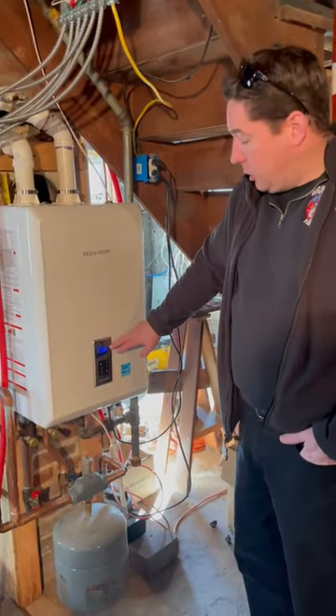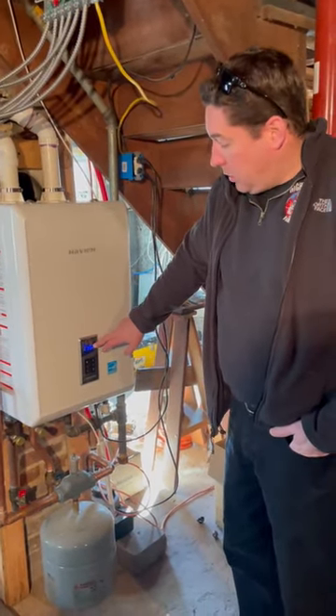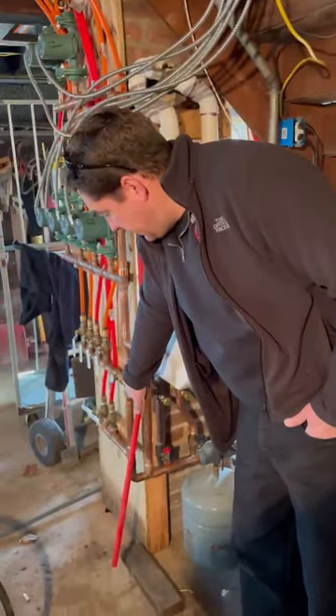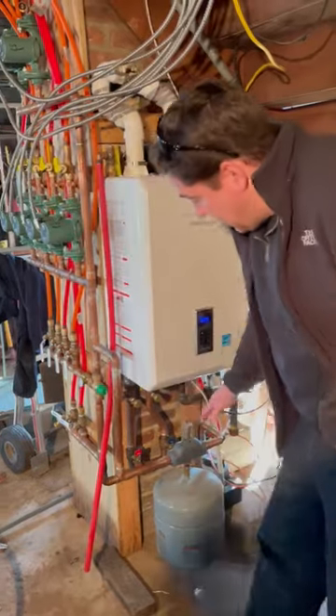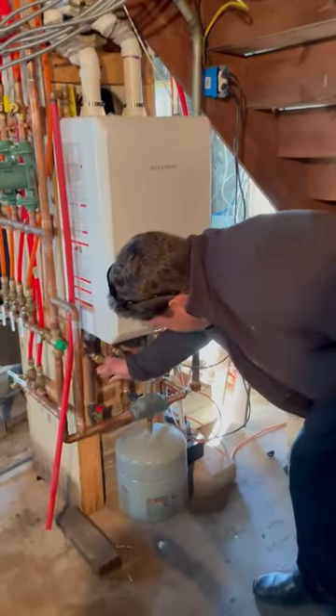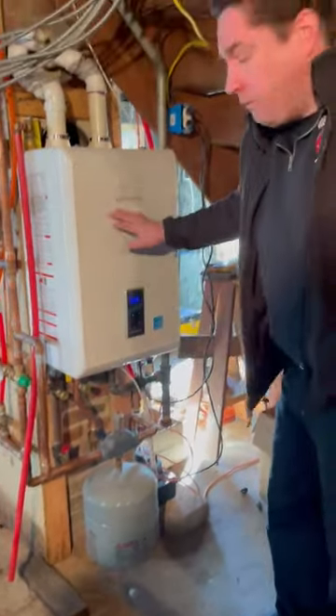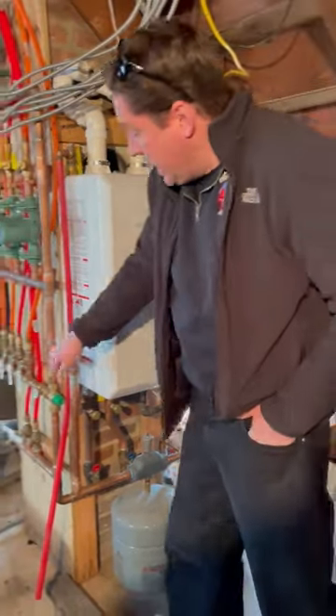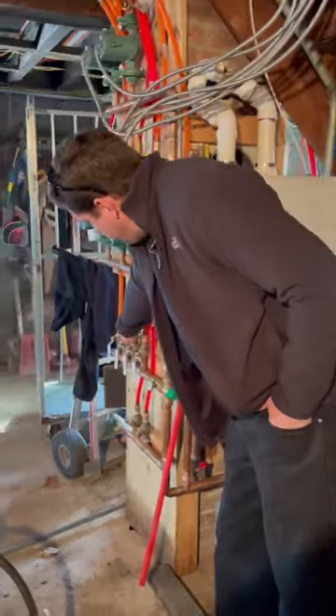My boiler is set to 165. My mixing valve is set to 120. I'm getting good flow here. This is the Navien manifold. This is an NCB240E, by the way. What my problem is, is that I'm not getting the flow through here, here, and here.